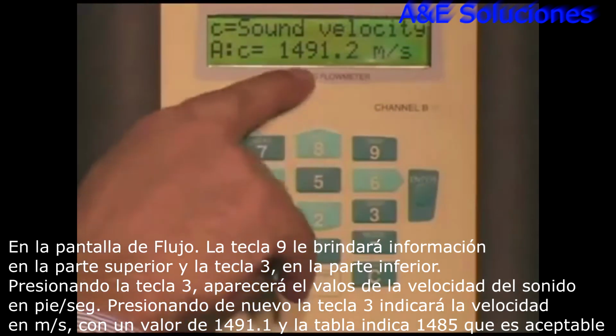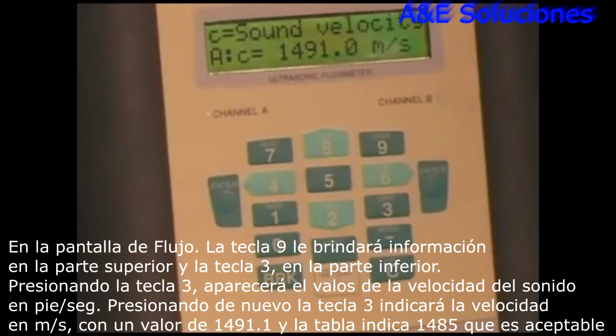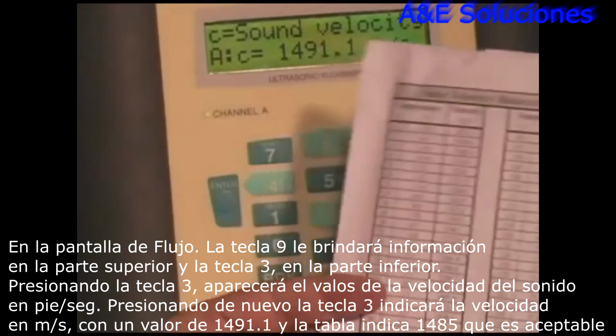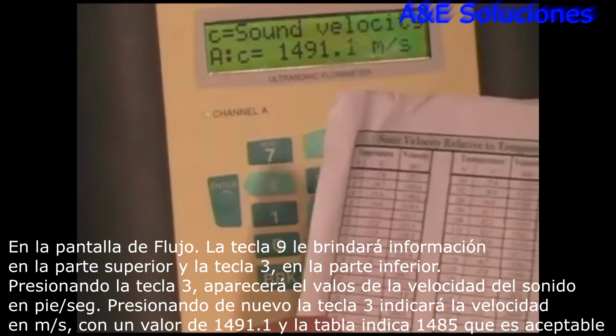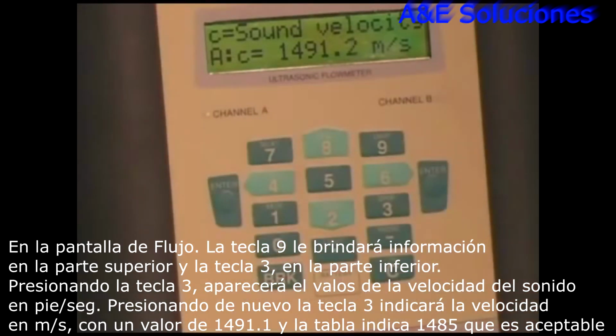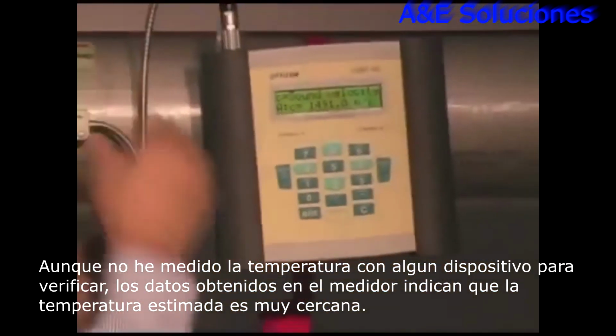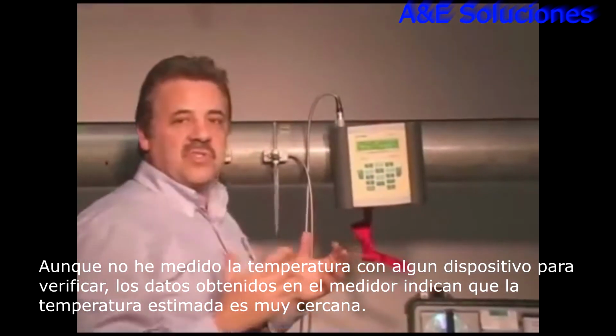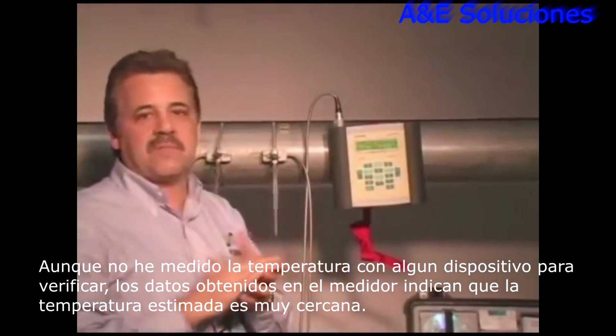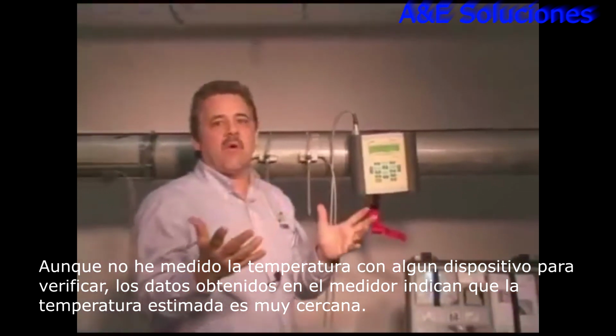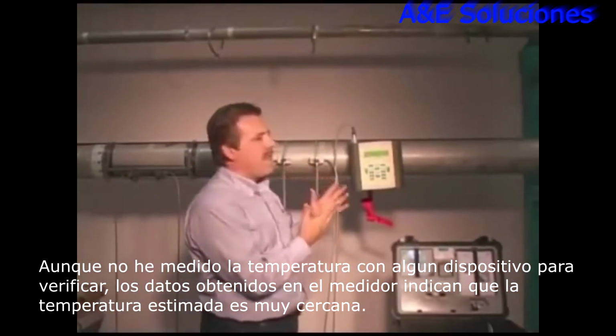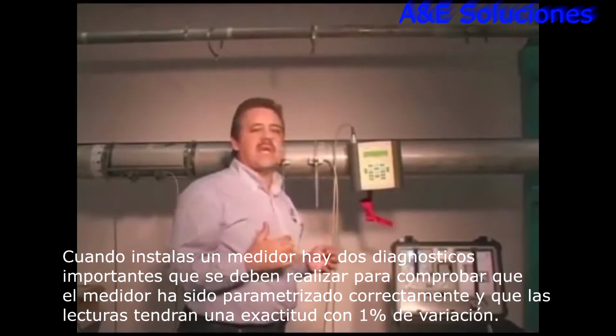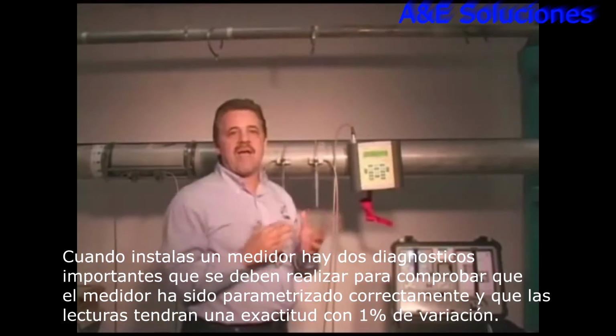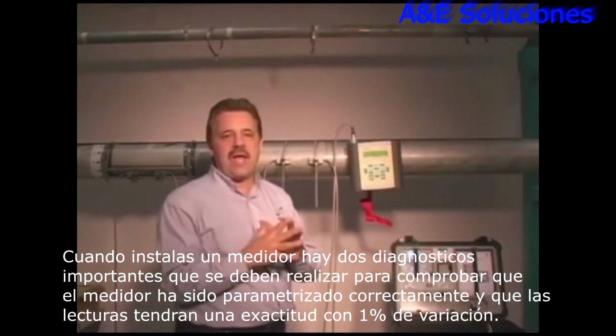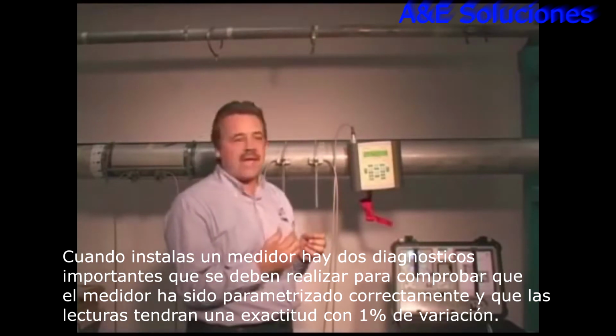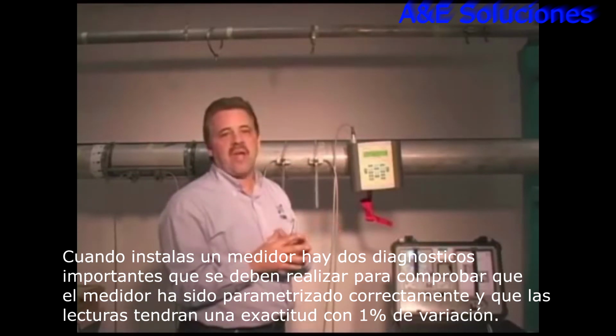And you'll see that we're getting a sound velocity of 1491. The table said that I should have, for 70 degrees, 1485. So that's pretty close. And I didn't actually measure this water temperature, but that tells me that I've installed the meter properly. And that's the biggest hurdle that you have to get over. When you install the meter, there's two main diagnostics that you're going to look to that tell you that I've done it right. And if you do it right and you're getting that proper diagnostic feedback, you can trust the readings. You're going to have pretty accurate readings.